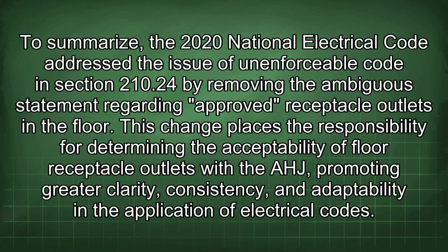To summarize, the 2020 National Electrical Code addressed the issue of unenforceable code in Section 210.24 by removing the ambiguous statement regarding approved receptacle outlets in the floor. This change places the responsibility for determining the acceptability of floor receptacle outlets with the AHJ, promoting greater clarity, consistency, and adaptability in the application of electrical codes.